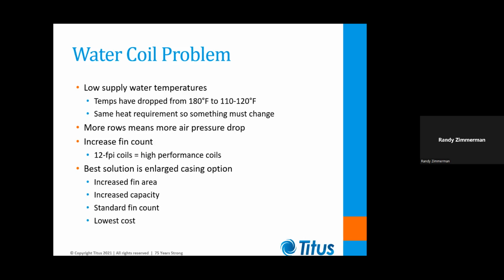Actually, the best solution for dealing with lower entering water temperatures is an option that we've added on our single duct boxes some time ago, and that's called the enlarged casing option. Like on a single duct VAV, that basically allows you to have an 8-inch inlet on a 10-inch unit casing with a size 10 water coil. So it upsizes the water coil by 1 cabinet size for the inlet duct on the box.